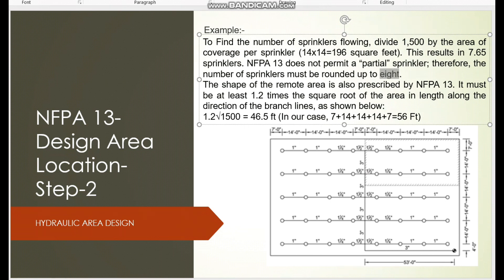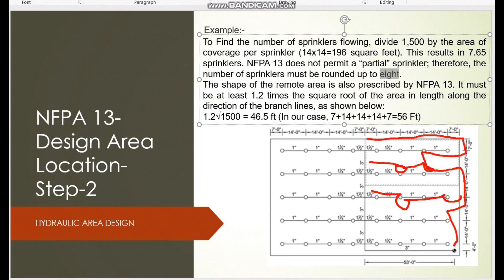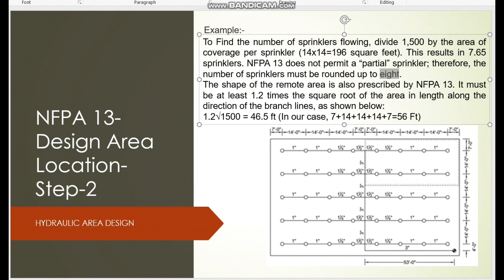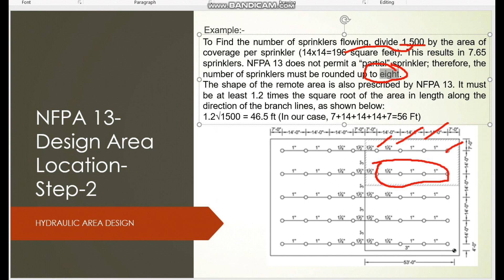This sprinkler count rule applies when sprinklers are placed with proper uniform spacing. However, in practice, if you have an irregular room, you cannot place sprinklers with equal spacing — some distances will be different. In that case, you cannot apply the simple sprinkler count rule. Instead, you must verify that the total area covered is at least 1500 ft² as required by NFPA 13. For our regular case, 1500 ÷ 196 = 8 sprinklers: 4 in the first row and 4 in the second.